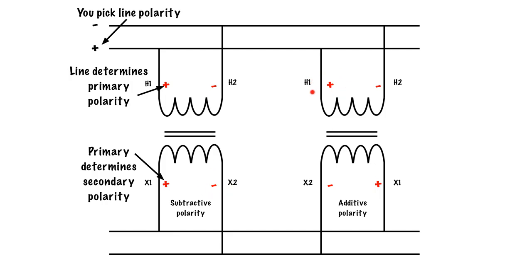Over here, I've got H1 is positive, which means that X1 over here is positive. So watch out for that because over here it was across the way. Over here, X1 is positive. H2 is negative. X2 is negative. So again, you pick the line polarity. The line polarity determines the primary polarity, and the primary polarity determines the secondary polarity.